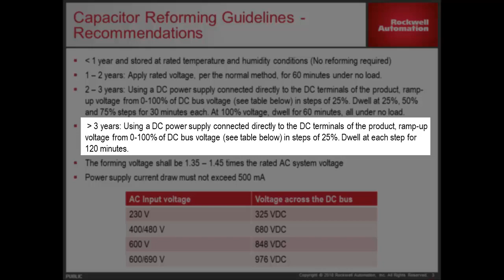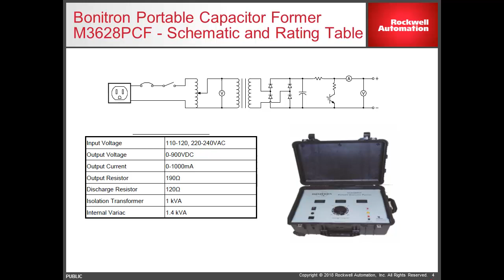For greater than 3 years, the drive should have incremental voltages applied to it at 25% increments, dwelling at each step for 2 hours at each step, and again, the drive should not run or modulate. There are several different tools that could be used to vary the voltage applied to the capacitors for reforming. One example of this tool is from Bonitron. This device can connect directly to the DC bus and vary the voltage as needed.